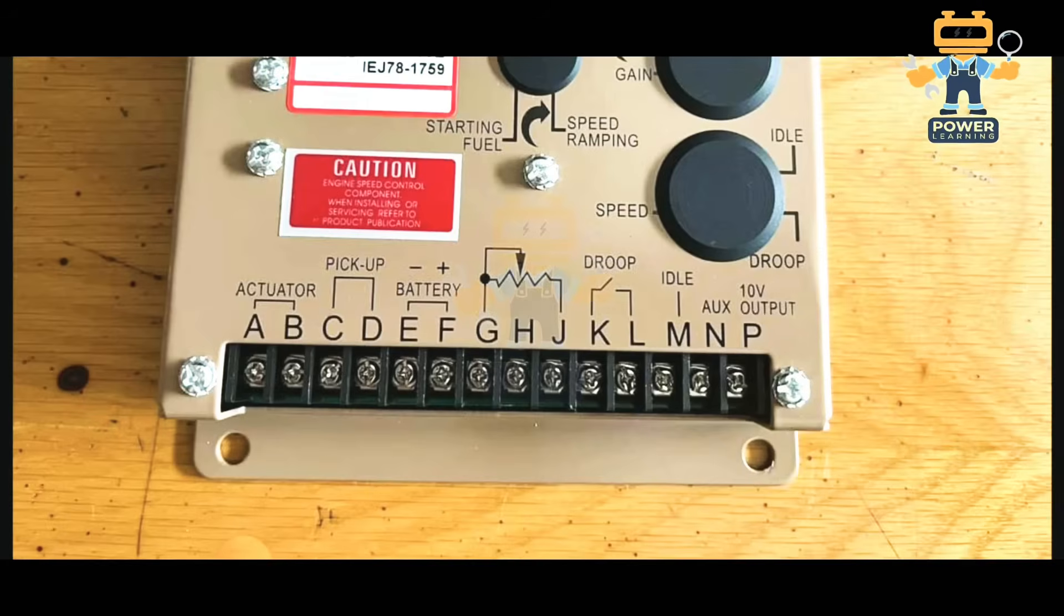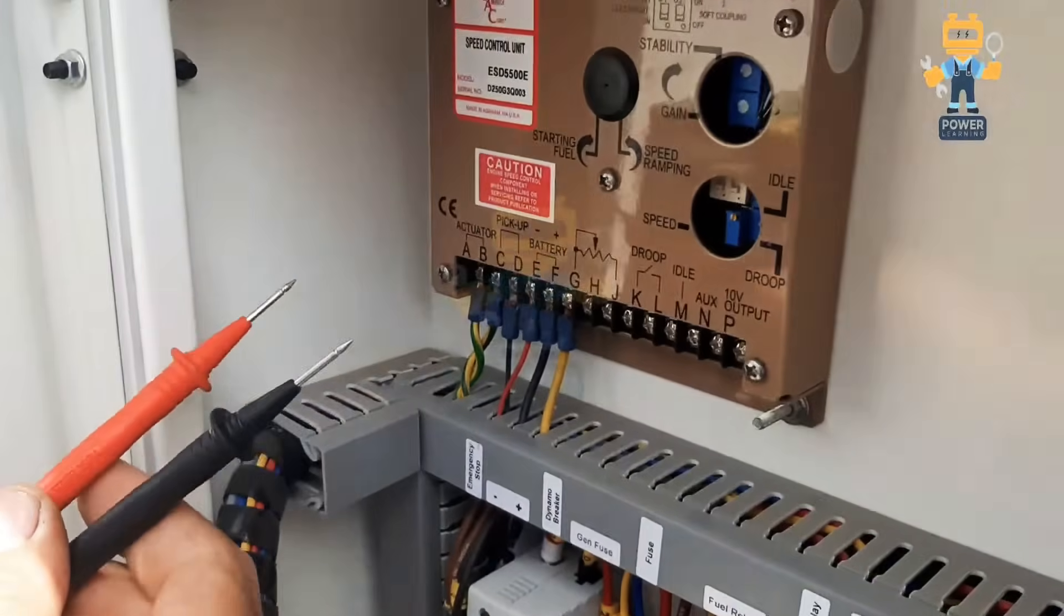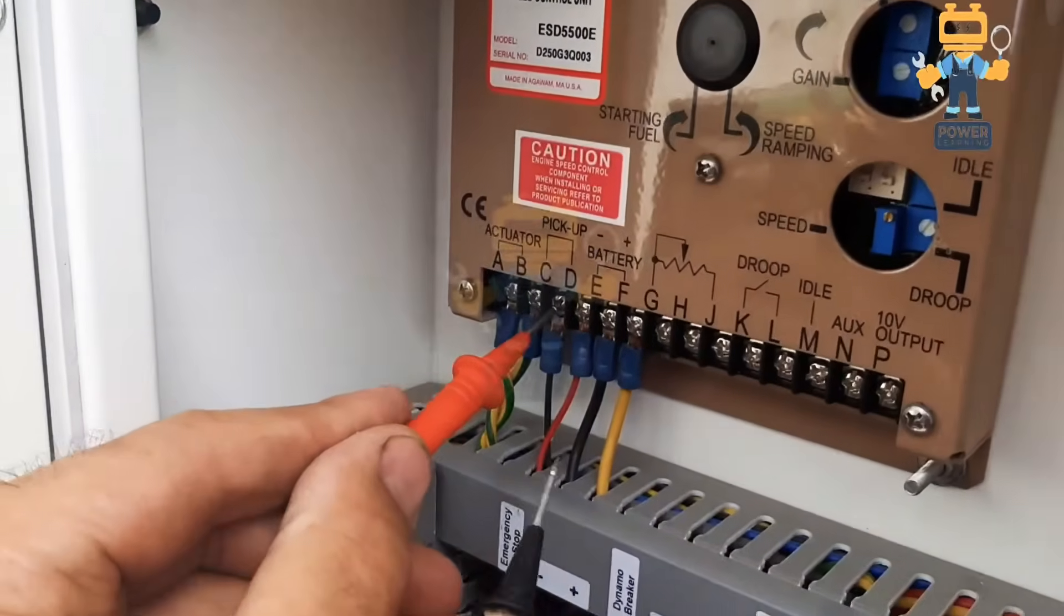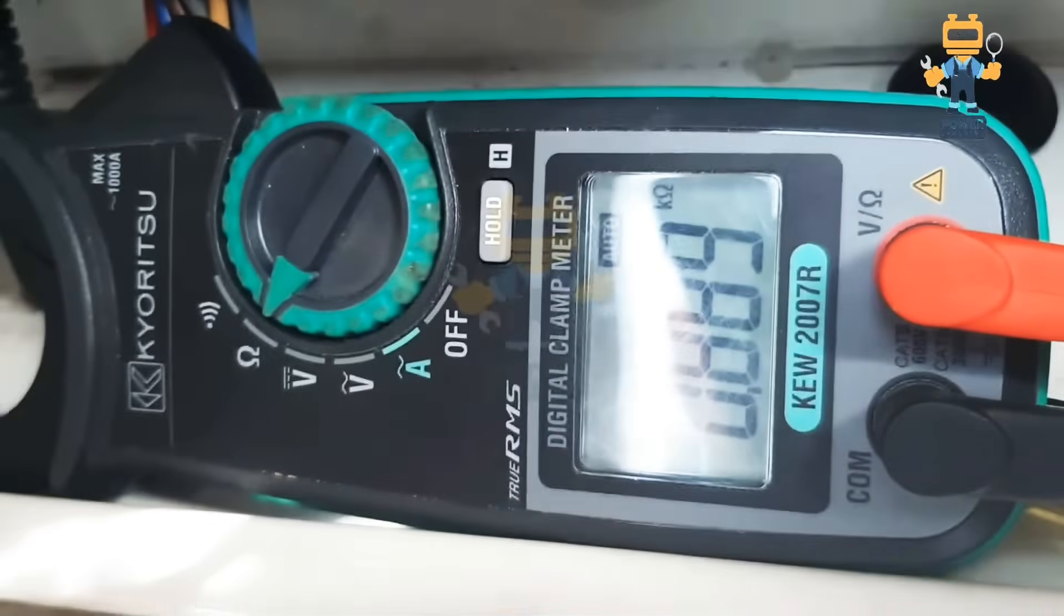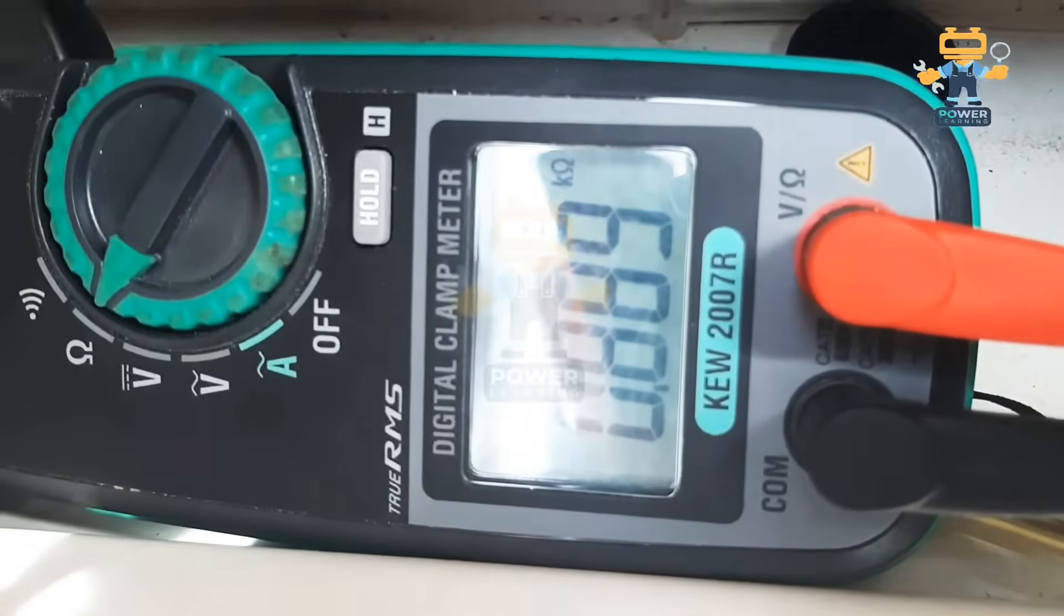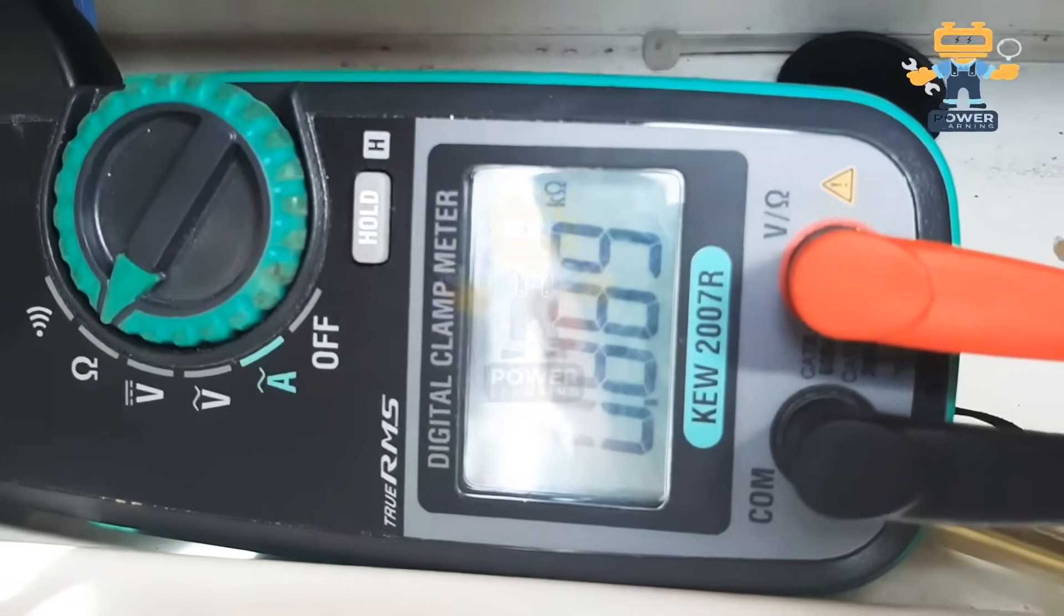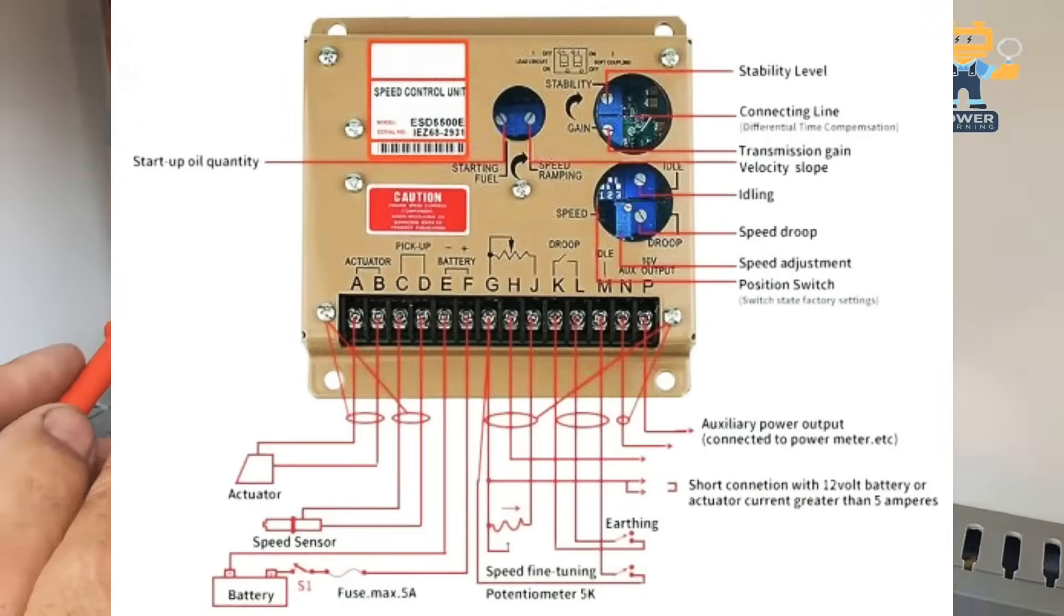While the engine is cranking or running, this MPU is giving AC volt signal to this controller. So this is an input of this controller - magnetic pickup giving AC volt signal to this controller during starting and during running of the generator. After getting this signal at the pickup point, the controller receives this as an analog input, AC voltage coming here.